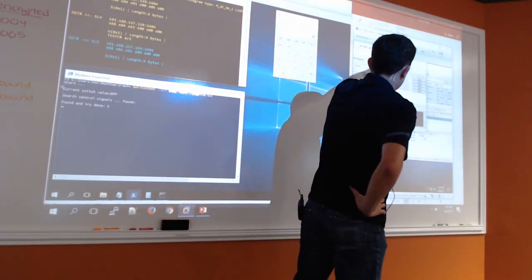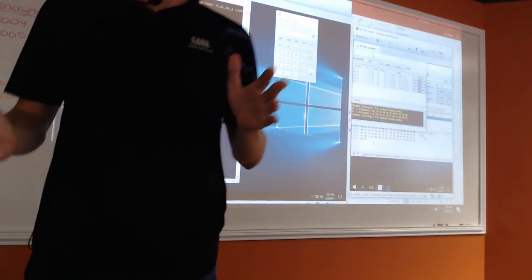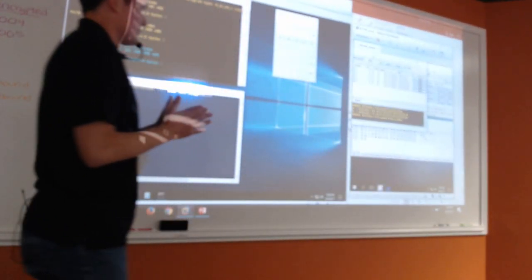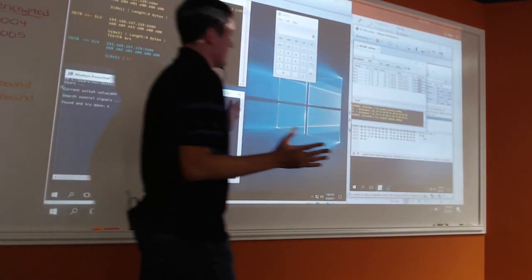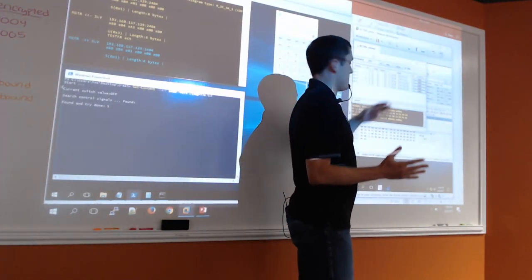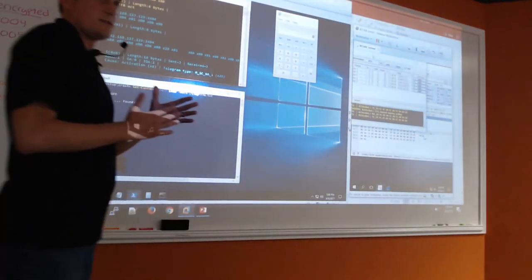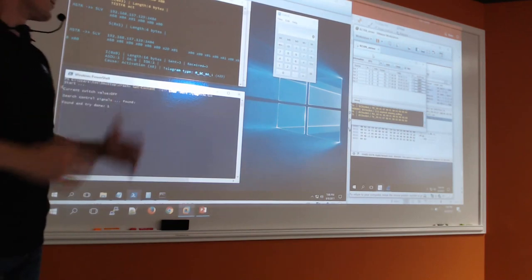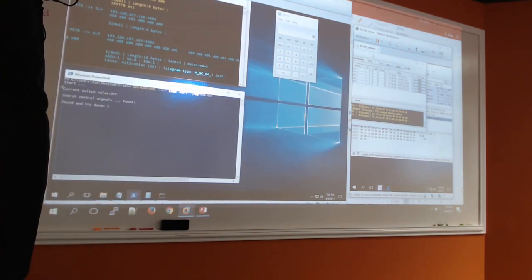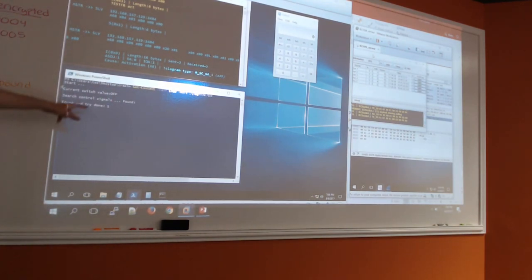So anytime you see this go to a zero, it means the breaker's being turned off, so that area is losing power. When you see 1, 2, or 3 turn to a 0, it means that breaker's opening and they're losing power. If it's a 1, it's closing, and that means there's actually power flowing through. So right now it just found register 1, it's looking for 2.